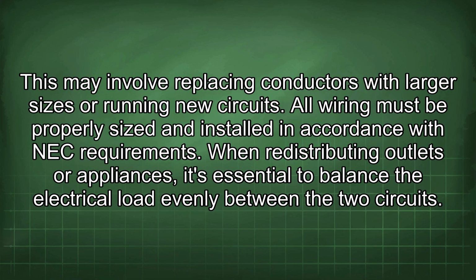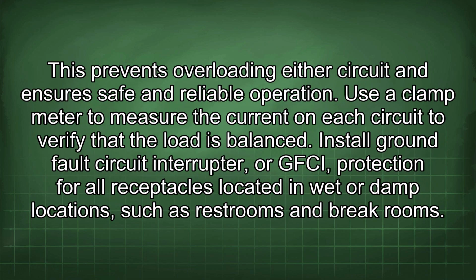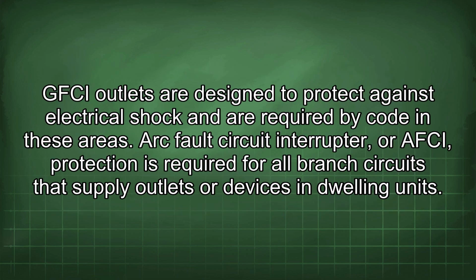When redistributing outlets or appliances, it's essential to balance the electrical load evenly between the 2 circuits. This prevents overloading either circuit and ensures safe and reliable operation. Use a clamp meter to measure the current on each circuit to verify that the load is balanced. Install ground fault circuit interrupter, or GFCI, protection for all receptacles located in wet or damp locations such as restrooms and break rooms. GFCI outlets are designed to protect against electrical shock and are required by code in these areas.